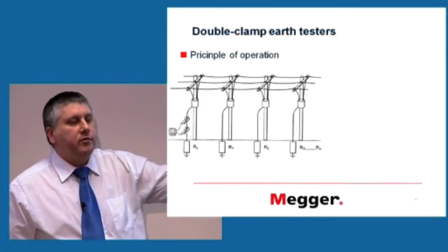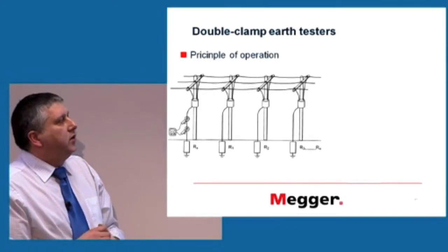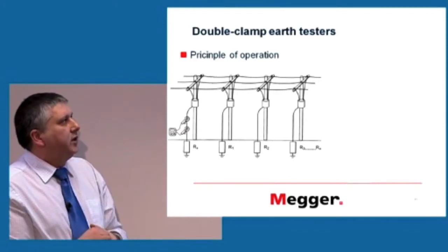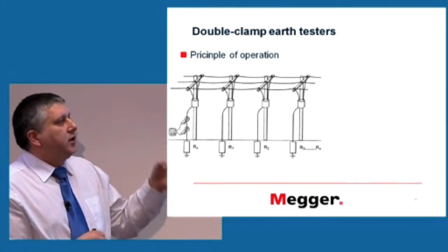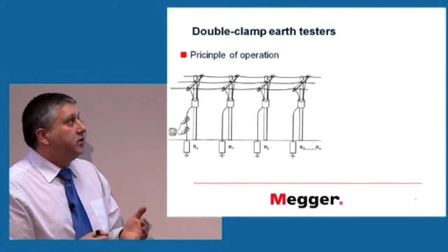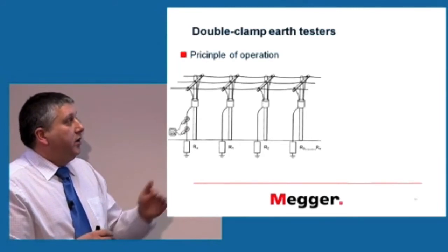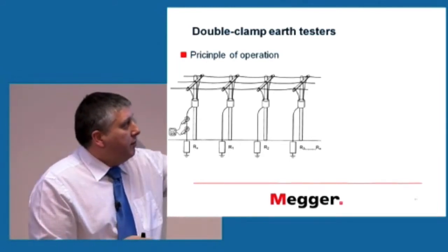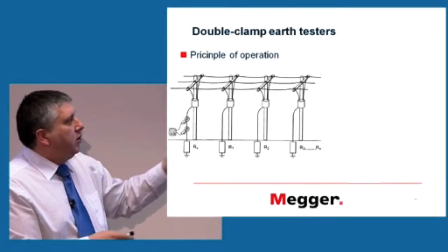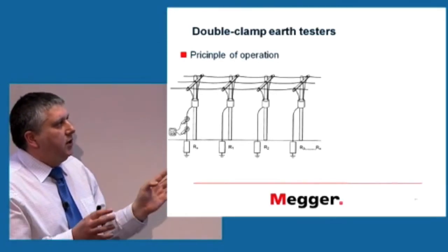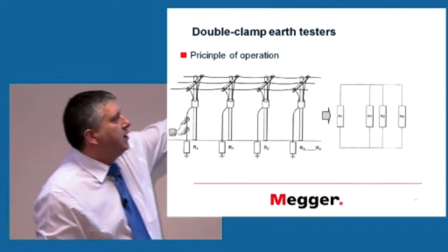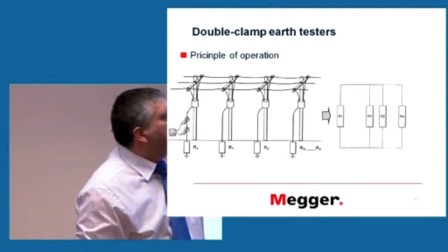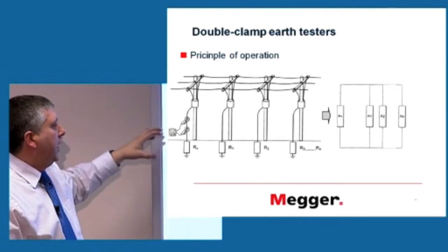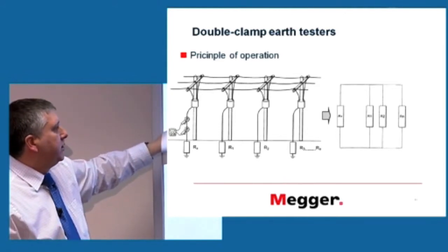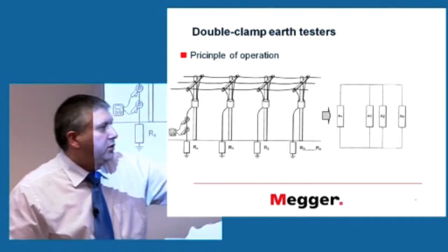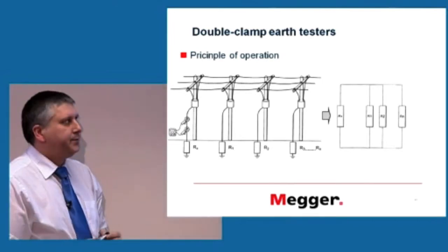So say we have a system. In this case, it's a number of poles carrying some overhead lines, each of which is connected to ground with some grounding electrode for safety. If we look at the electrical diagram, it looks more or less like this, right? We have our main electrode, which is then shorted with all the others at the top, and there is some ground resistance, and all of them are then shorted by the ground. So the equivalent circuit will be something like that.